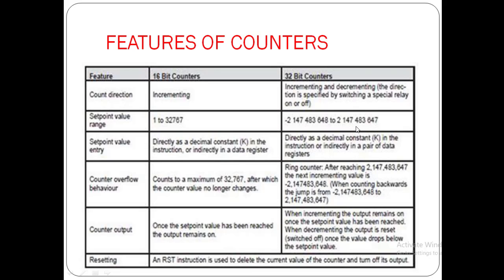The set point value can be entered directly as a decimal constant K in the instruction, or indirectly in a data register. In a 32-bit counter, you can store it directly as a decimal constant K or indirectly in a pair of data registers — it needs two registers. A 16-bit counter requires only one register.